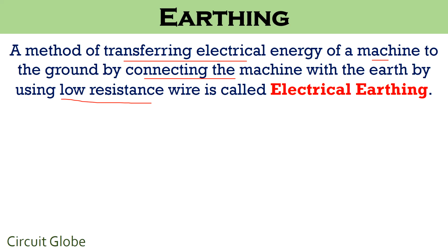You must note here that no current flows through the earthing wire in normal conditions, but the discharge of current takes place through the low resistance wire in abnormal conditions. It is used as a precautionary measure to reduce the chances of danger to devices and humans. We will definitely understand more about this, but let's first see how earthing is done.